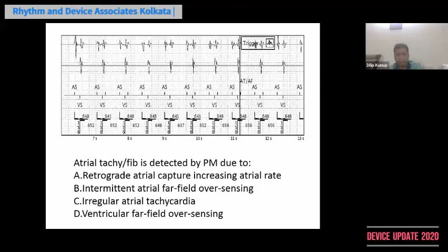What is the solution? The solution would obviously be to decrease the atrial lead sensitivity so that it does not sense this particular far field signal. Actually, during implant itself, while positioning the atrial lead, we ask our industry representatives or technicians to look at the screen and tell us whether we are seeing this ventricular far field signal on the atrial lead at all or not. If the ratio is less than... next slide, please.